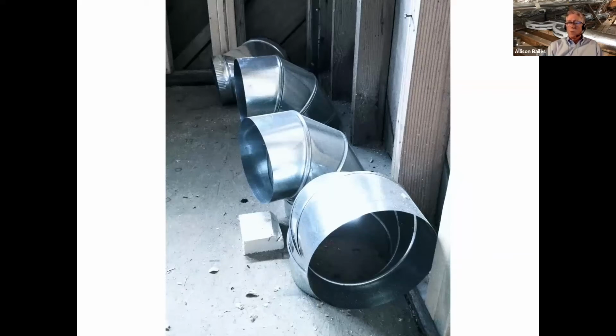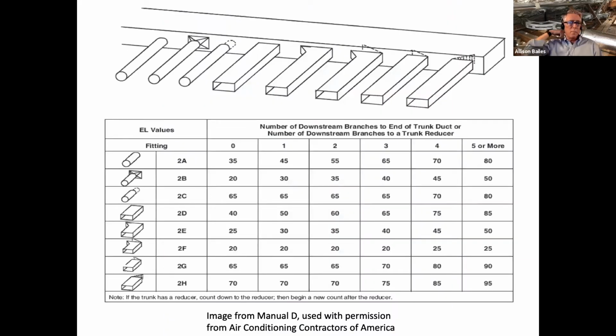And so going back to the myth that you can't put too long of a duct system on a low static air handler, it's not the actual length that matters, it's the total effective length. And the fittings determine that way more than the actual length of the duct system. So here's an example of takeoffs from a trunk line. If you're doing these different kinds of takeoffs, you can see that there's a table here, and we don't need to go into all the details of it, but there are different kinds of takeoffs, and where they're positioned on the trunk line has an effect. So if you look through here, the low end of this is 20 feet. So that one takeoff on the trunk line is 20 feet. Or you could choose a really bad one that's 90 or 95 feet. So that one fitting is equivalent to 90 or 95 feet of straight duct. That's horrible.